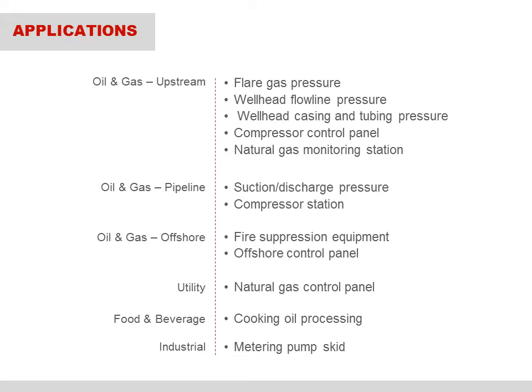If your plant has a Modbus RTU network and you need to monitor water pressure, air pressure, hydraulic pressure, steam pressure, or any other process pressure, the 815 PT will fit in those tight, dangerous, hazardous, hostile areas of your plant. The 815 PT's robust, stainless steel, explosion-proof housing has the right stuff. If you need all of the above, well, the 815 PT Smart Pressure Transmitter offers all these features as standard. There is no need to choose. They are readily available for you to use.